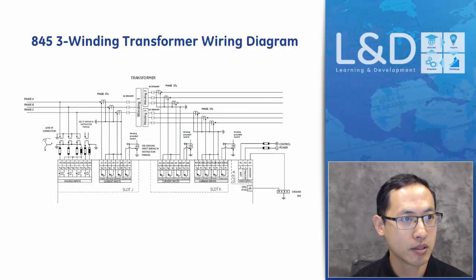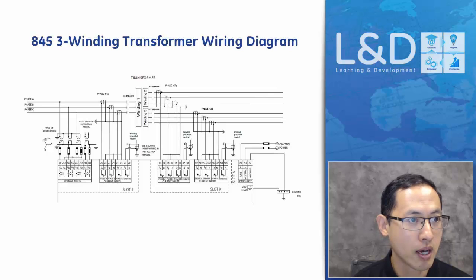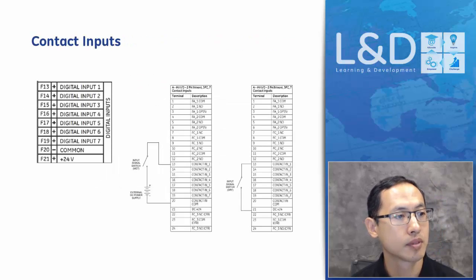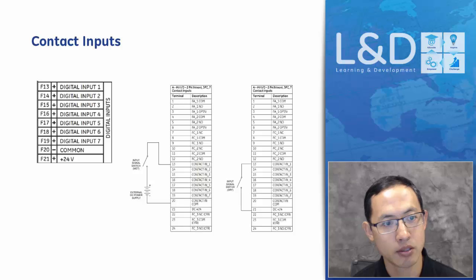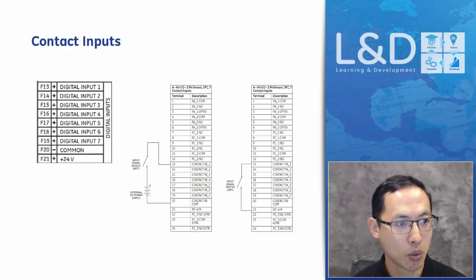And for the 3 winding transformers, the J slot will be used for CT1, the high side CT, and the VTs, and the K slot will be used for the winding 2 and winding 3 CT inputs. For the contact inputs, there are 2 ways of wiring them. One is wet mode and another is dry mode. When wired in the wet mode, they use an external DC power supply to assert a contact input. So in that case, terminal 20 will be used as a common.